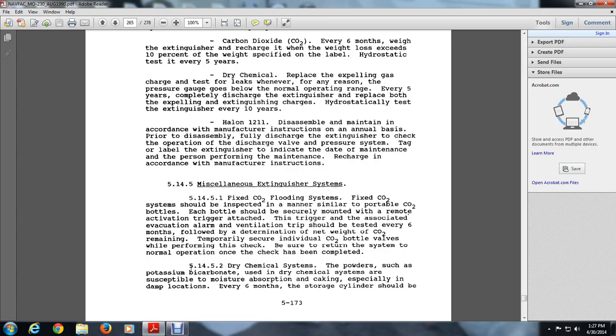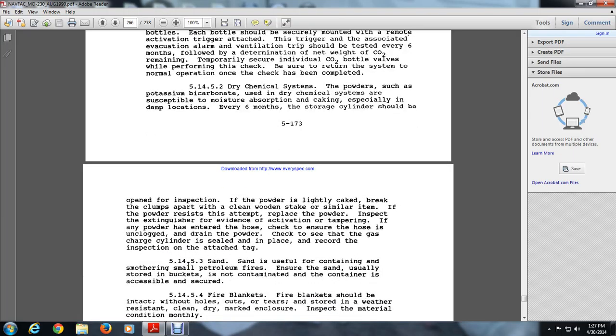5.14.5.2 dry chemical systems. Powders such as potassium bicarbonate used in dry chemical systems are susceptible to moisture absorption and caking, especially in damp locations. Inspect every 6 months, and storage cylinders should be opened for inspection. Powder should lightly break into clumps, and a piece of clean wood or a stake or similar item can be used. If the powder resists, replace it. Inspect the extinguisher for evidence of activation and tampering. Check the hose to ensure it is unclogged and drained of powder, and check to see that the gas charge cylinder is sealed with a red cord and the inspection attached to the tag.